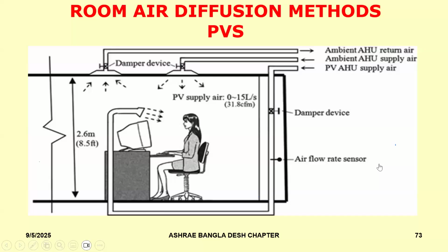Now we come to the other method, which is our personalized ventilation system. Now this is something that is slowly getting traction. So far it's been largely relegated to research zones, but now we are finding increased acceptance, and it is being used in many commercial applications. So just to give you an overview of this, we also have a duct which is bringing in the air and directly feeding into the breathing zone. You know, I referred to the aircraft earlier. So this is something similar to that. So this is only bringing in the outside air, whereas the rest of the room load is taken care of by a normal system like this.